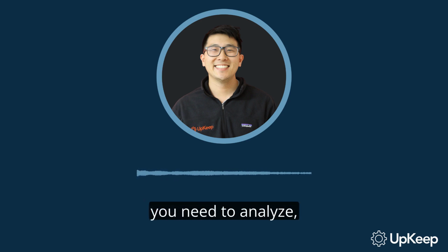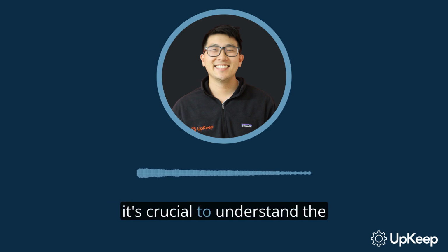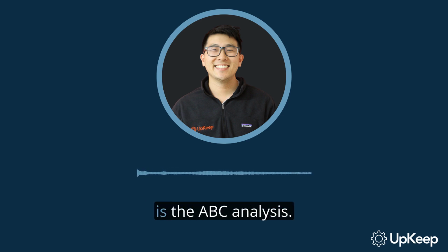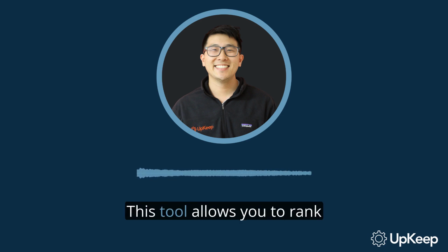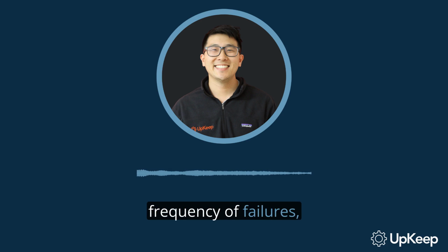First things first, you need to analyze, rank, and prioritize critical failures. To prevent breakdowns, it's crucial to understand the failures on your critical assets, where they come from, and their impact. A popular tool for this is the ABC analysis. This tool allows you to rank 3 factors on a 10-point scale: frequency of failures, how hard it is to detect the failure, and the failure's impact on your overall operations.